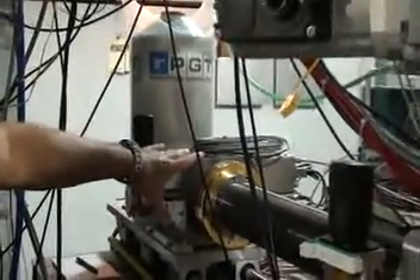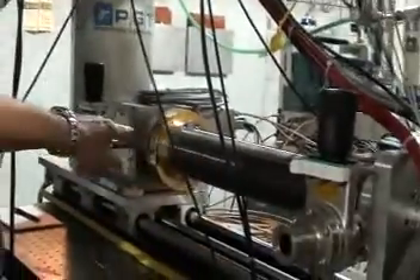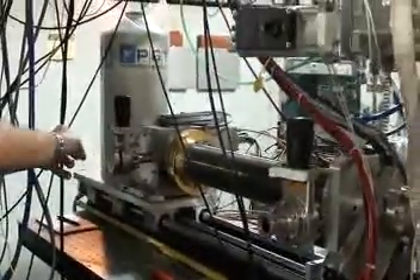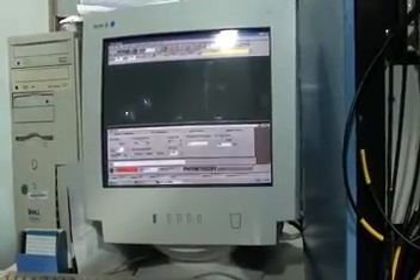This is the vacuum chamber for our system. The end cap is inside this bellows under vacuum right now. We're fully retracted out of the column with the gauge valve closed for preparation for the sampler. This is a motorized stage driven by a stepper motor and controller configuration with an end stop on each end. We are measuring the resolution on the Phosphorous 2 keV and the Sodium 1 keV line. The specification for the Phosphorous is 89 eV, and the specification for the Sodium is 79 eV.